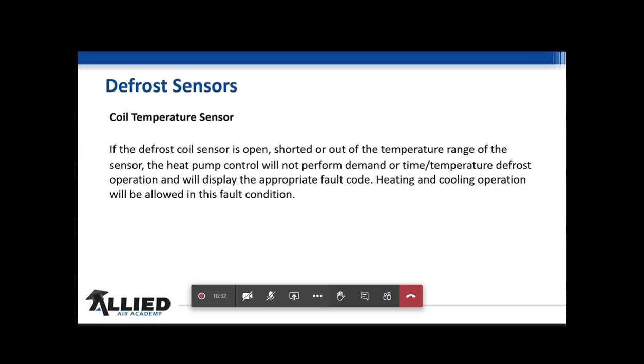So it's important for this code, if the coil temperature sensor's out, that we take this call first, because we don't want ice to build up, get stuck on the fan, burn a fan motor up, or anything of that nature. So the difference between the two and when it goes out is pretty critical to the thinking and the mindset of the person going out there working on this.